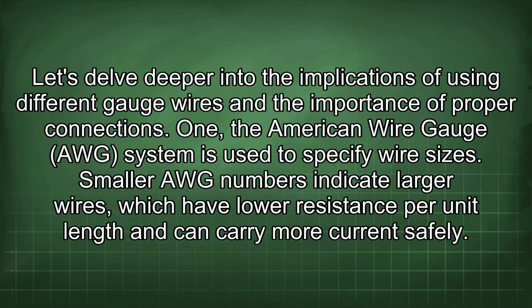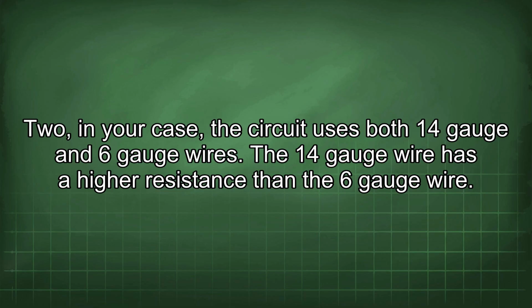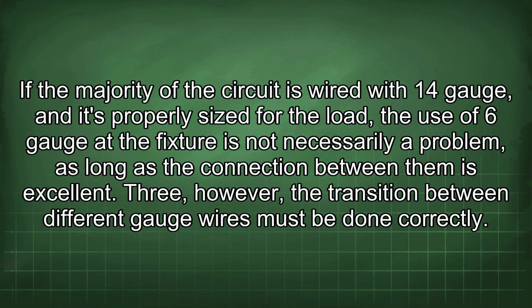The American wire gauge, AWG, system is used to specify wire sizes. Smaller AWG numbers indicate larger wires, which have lower resistance per unit length and can carry more current safely. 2. In your case, the circuit uses both 14 gauge and 6 gauge wires. The 14 gauge wire has a higher resistance than the 6 gauge wire. If the majority of the circuit is wired with 14 gauge and it's properly sized for the load, the use of 6 gauge at the fixture is not necessarily a problem as long as the connection between them is excellent.